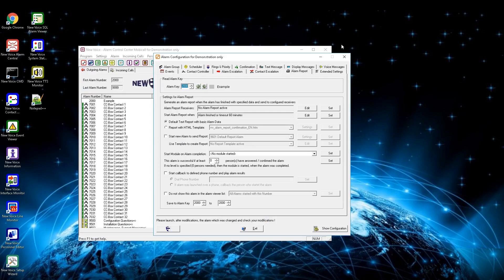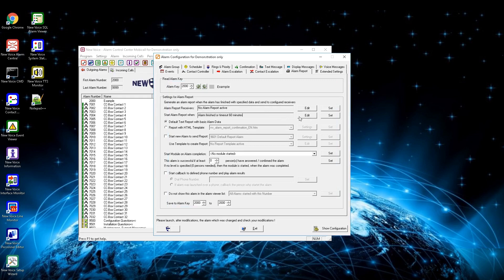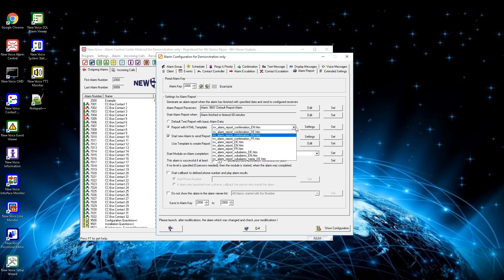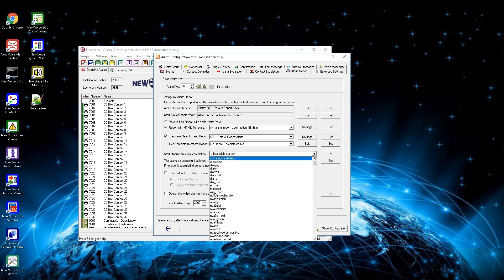Within the alarm report settings window, MobiCall can be configured to send a report from a finished alarm to specified receivers, to inform them of the confirmation status. At the setting alarm report receivers, press on edit to define if you want to send the report to a printer, email recipient, or fax device. At the setting start alarm report when, define the time when the report should be sent. By default the report is sent as text with basic alarm data, but this can be changed to send with an HTML template — the templates can be adjusted as needed. By activating the checkbox below, an alternative alarm can be started to send the report, allowing the report to be sent to receivers that are not email, fax, or printers. Once active, you need to define a message template for the report — by default English and German templates are already available.